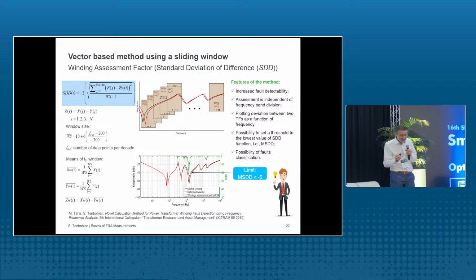But the basic problem is still, what are the different frequency ranges which I should investigate? And this is dependent on the size of the transformer. You can imagine a big transformer has lower resonance frequencies than a small transformer. So these frequency ranges are dependent on the transformer size. And we suggested a new algorithm where we use just a sliding window. We move a window over the full frequency band and calculate the value of the index in each window, and then this brings us this green curve.